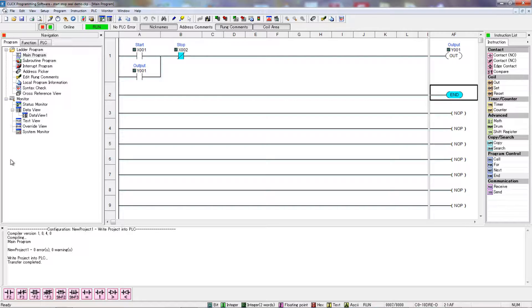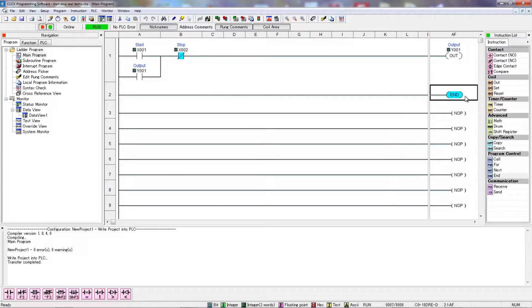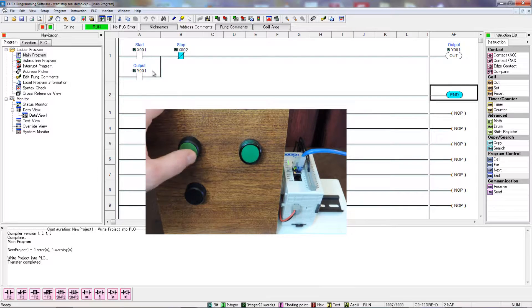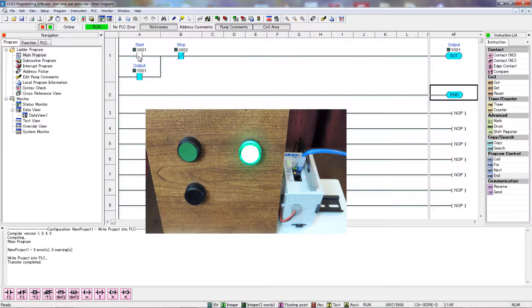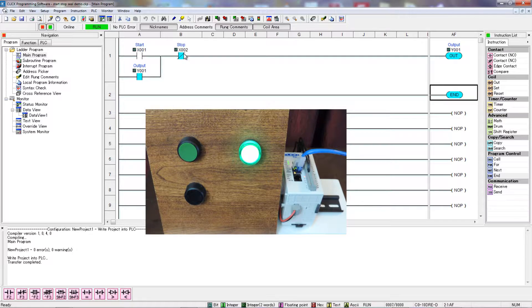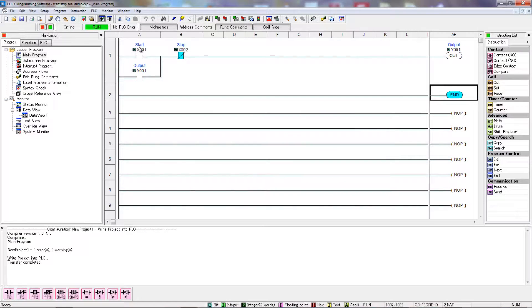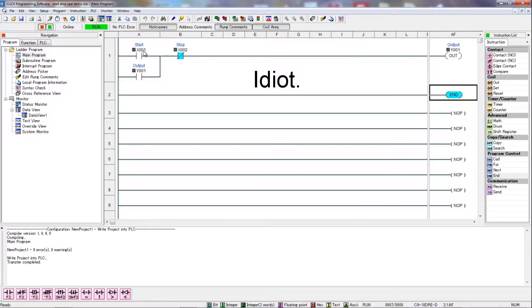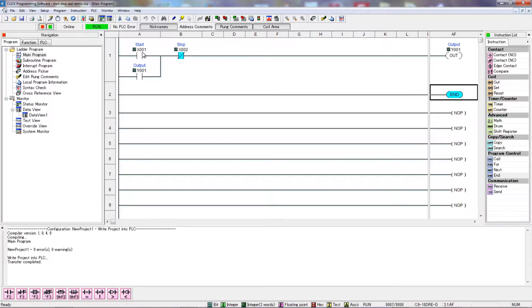So we can see the program's downloaded. It's in run mode, meaning the PLC is running. And it's indicating the parts of the program that are active that are being hit upon here. And so, if I press this start button here, which I will do, you can tell that a momentary contact has caused this to actually latch on. And so, now we can also press the stop button. And that momentary contact of the stop has caused that to turn the output off or cause it to unlatch. And so, as it is, it's just a basic. You might use this for something like a motor starter or something like that. It's kind of like I've said before, a primitive piece of ladder code. But where it can get interesting is if we expand it and we use some other functions with it.